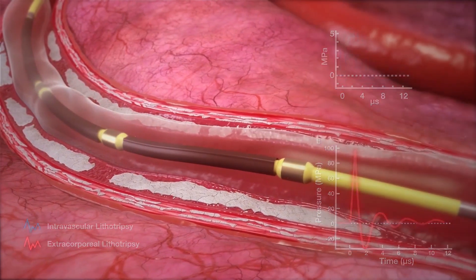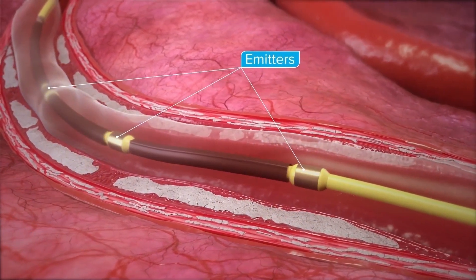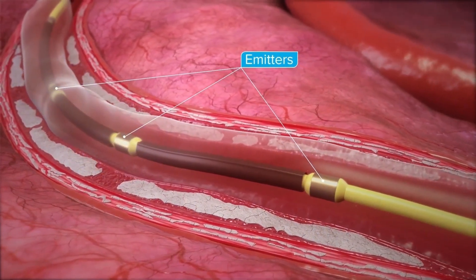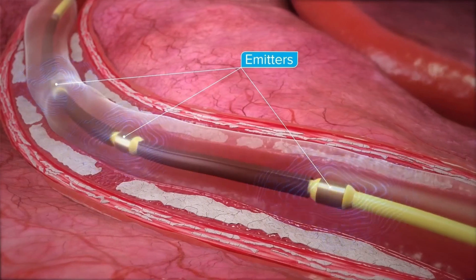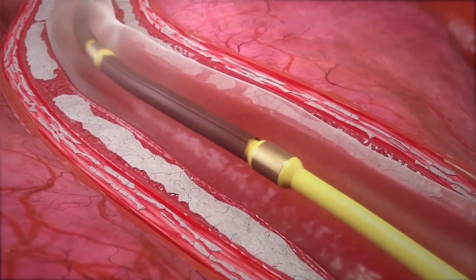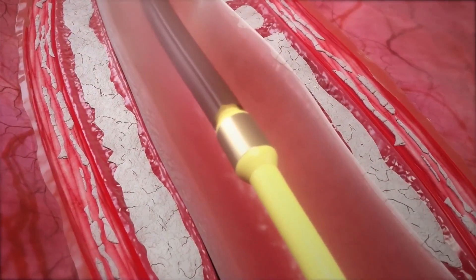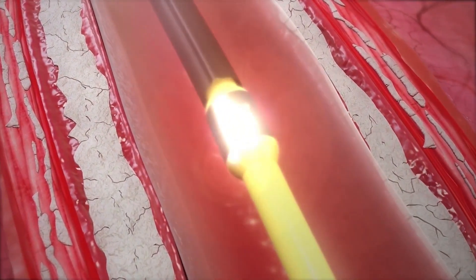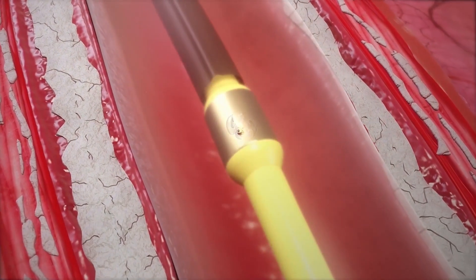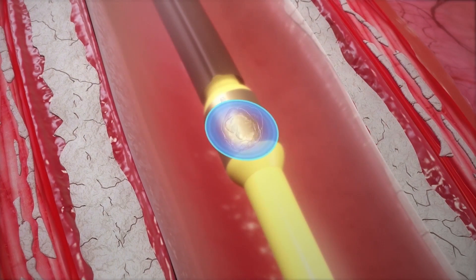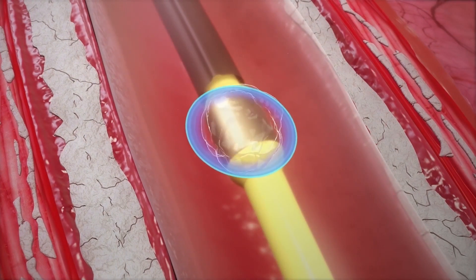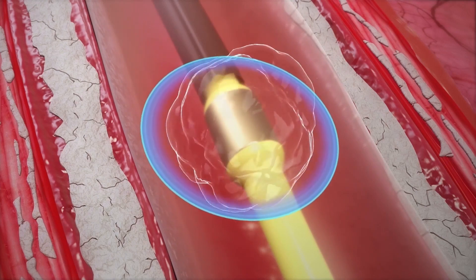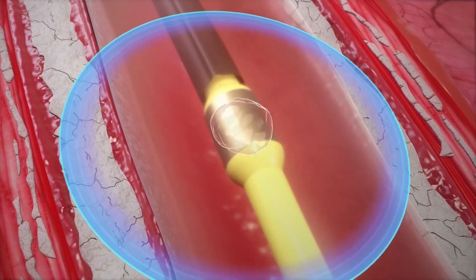To create an IVL shock wave, a series of emitters are arrayed within a balloon angioplasty catheter. The emitters fire electrical impulses across electrodes, which result in a plasma discharge, creating a vapor bubble that rapidly expands spherically, creating the initial shock wave.